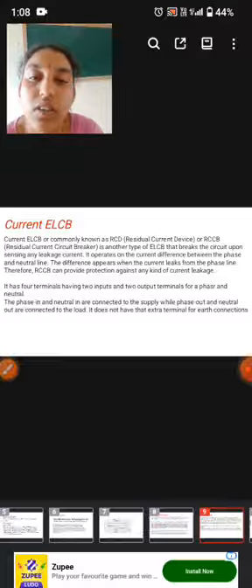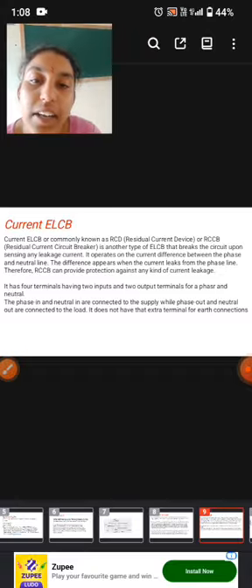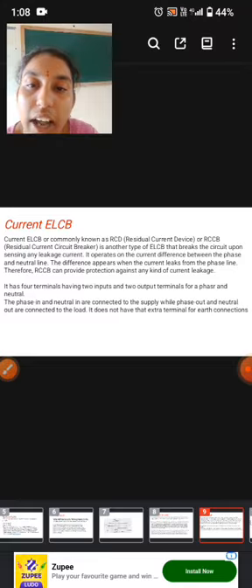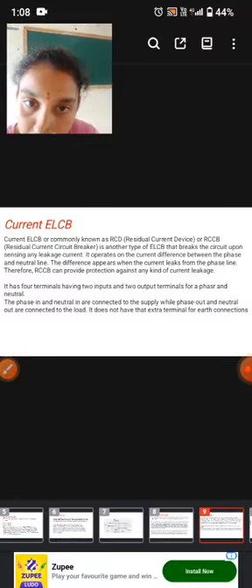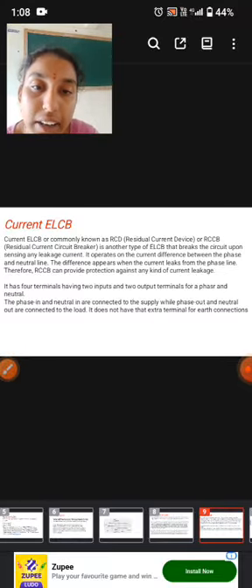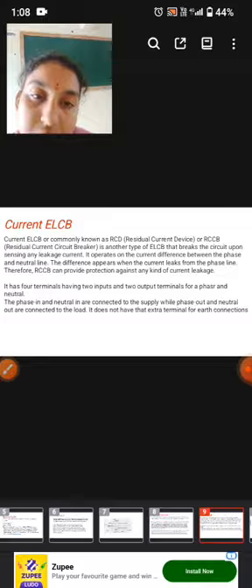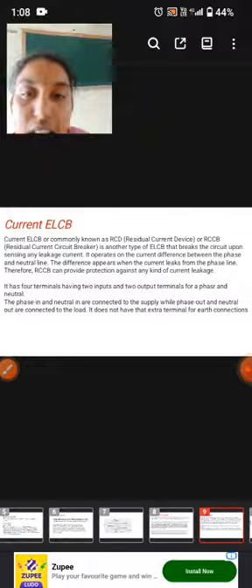Now we'll look at current ELCB. Current ELCB is also known as RCD, residual current device, or RCCB, residual current circuit breaker. It is another type of ELCB that breaks the circuit upon sensing any leakage current. It also operates on the current difference between the phase and neutral line.